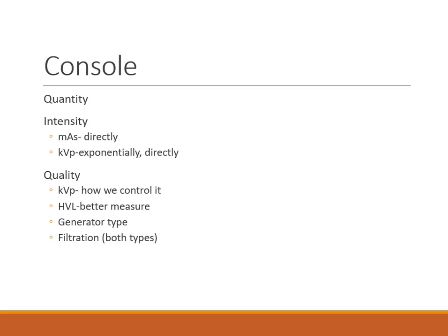What that means is that for every mAs that you generate, you should have a specific mR. But since we've got that added layer of filtration on the inside, naturally as the tube ages, your output's going to go down.